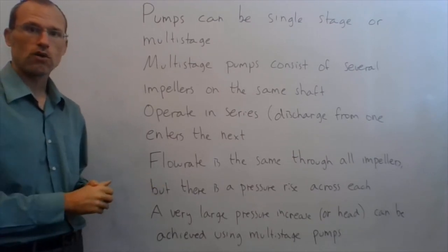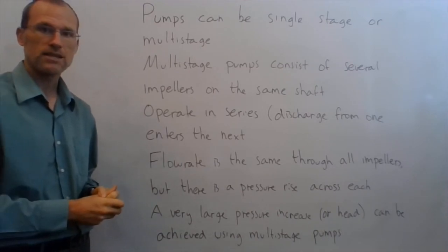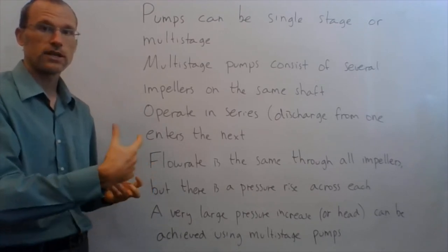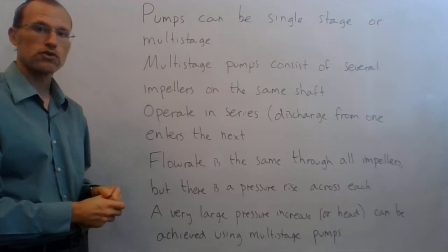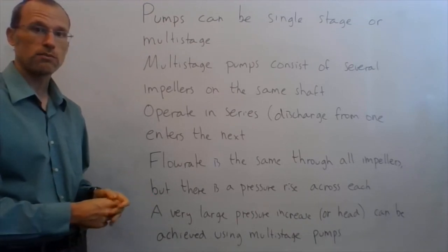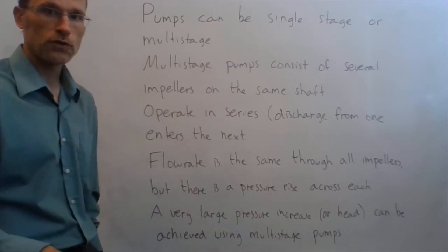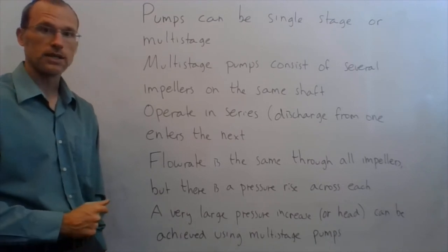The flow rates will be the same through all the impellers, in conservation mass can't go anywhere else, but each time I go through these impellers I get a new pressure rise, and so could have a very large pressure rise over the entire multi-stage pump through all these different impellers. So if you're looking for a really large pressure difference or a head, a multi-stage pump can give you that.